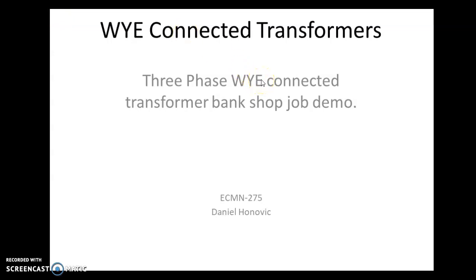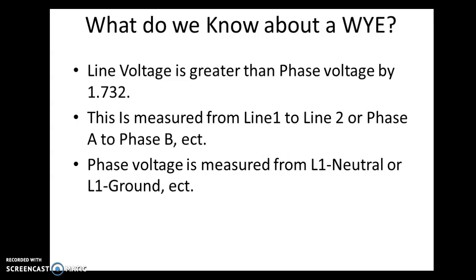To this point, we have explored a little bit about how transformers work, how to phase them out, what it means for coil polarity and how to identify that, as well as overall transformer functions in a Y connection or a delta connection. So what do we know about a Y connection? We know that line voltage is greater than phase voltage by the square root of 3, or 1.732.